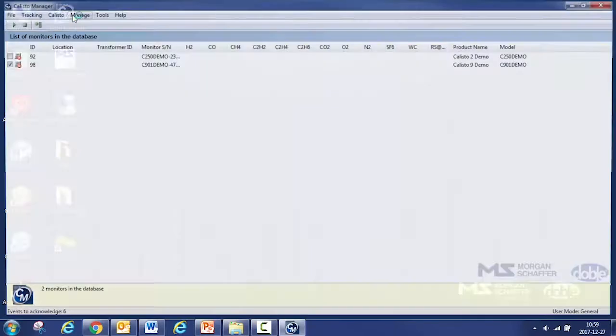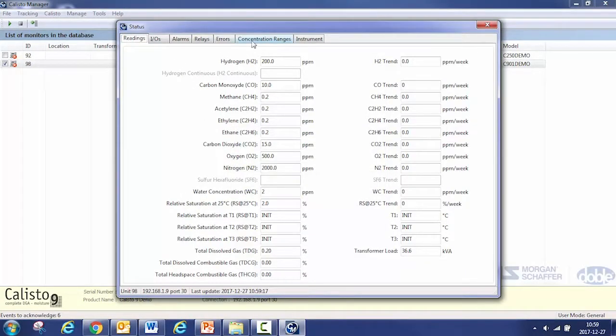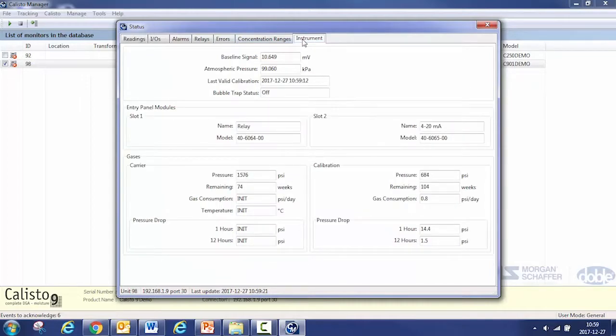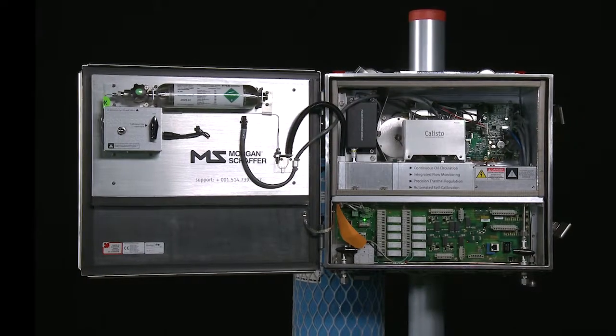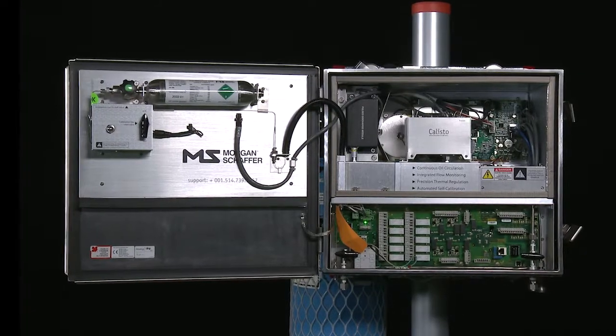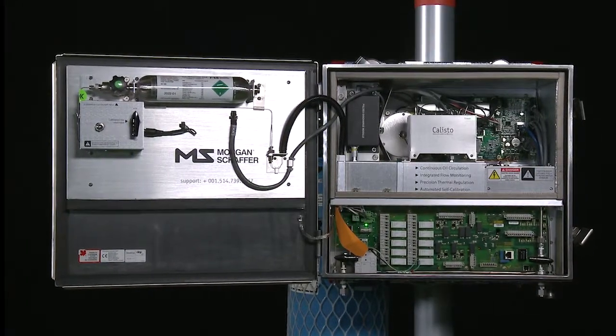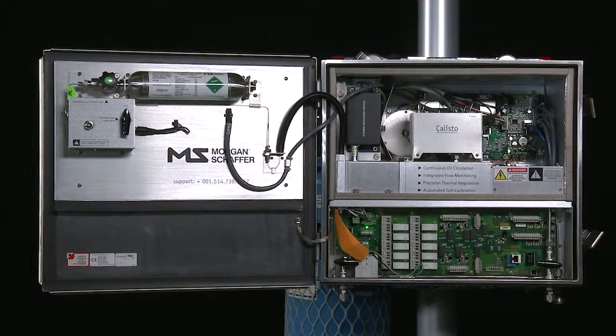Remember to enter the new calibration gas numbers using Calisto Manager. Note that this step will be explained in the configuration video. The calibration gas cylinder change is now complete. The unit will automatically resume operation in about 1 hour.